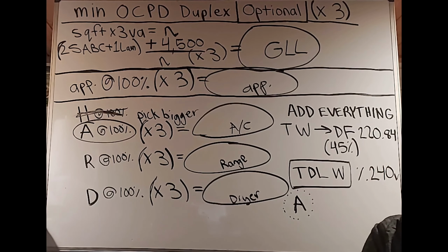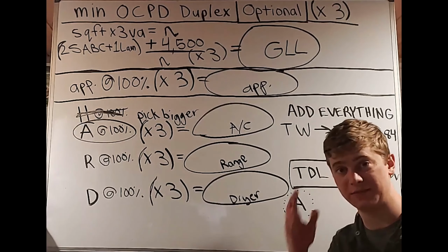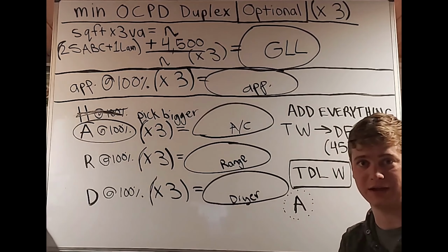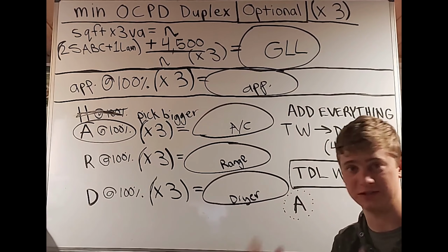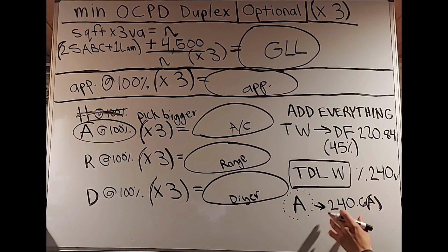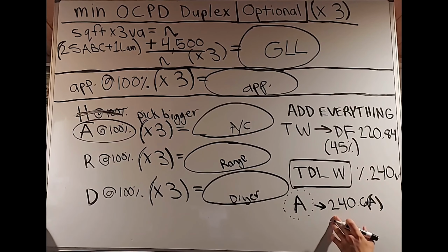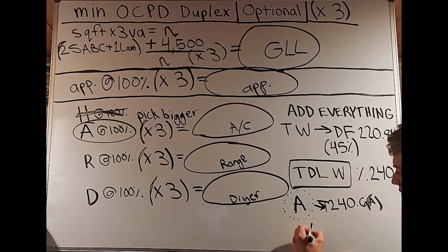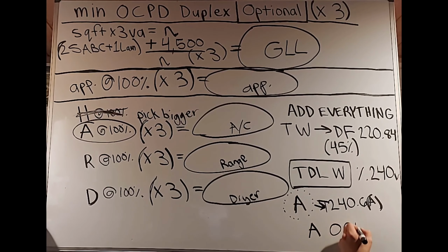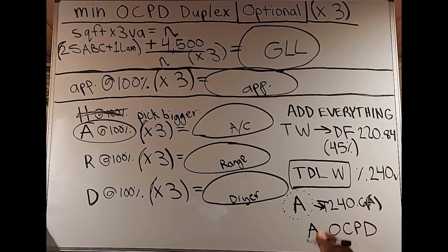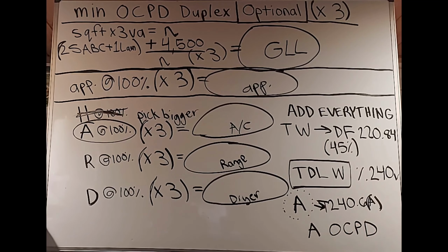So that's why it's good to also watch the follow-up videos that lead up to this video, because I'm trying to summarize some of the things that I already explained in my other videos, sometimes mentioning them in multiple videos by now. And after finding that number in table 240.6a, then we're actually going to know our amp rating for our overcurrent protection device, or in other words, our circuit breaker, which is our circuit breaker for our service. So it could also be called our service rating. So as we see, that's an amps for the overcurrent protection device.